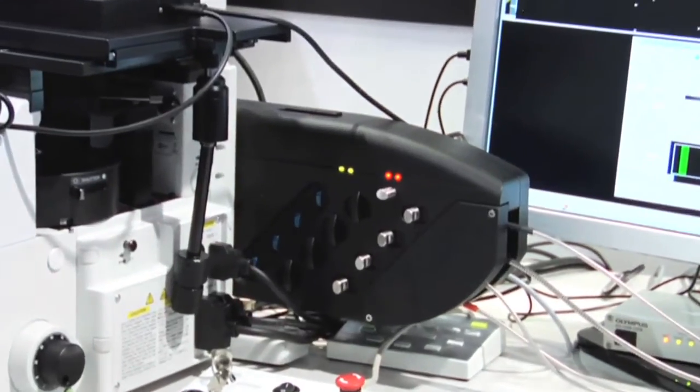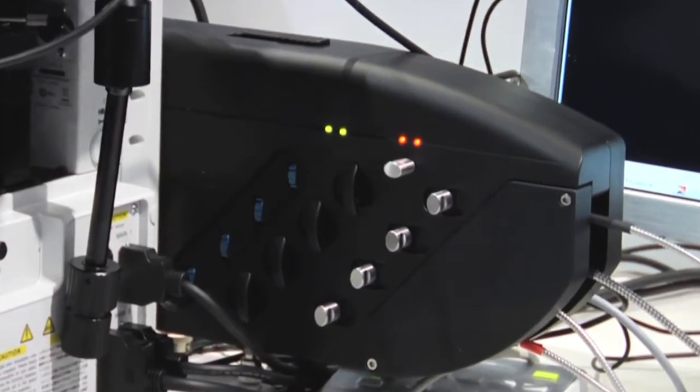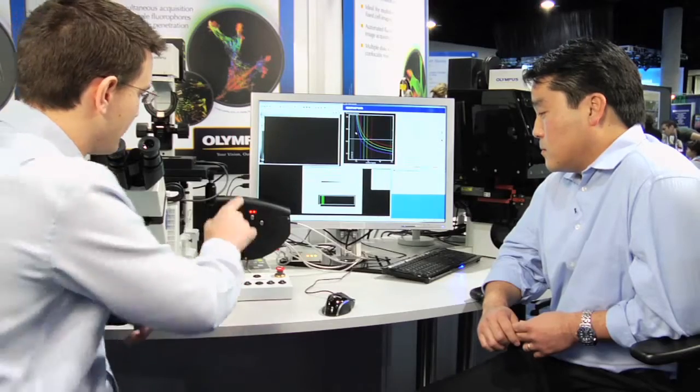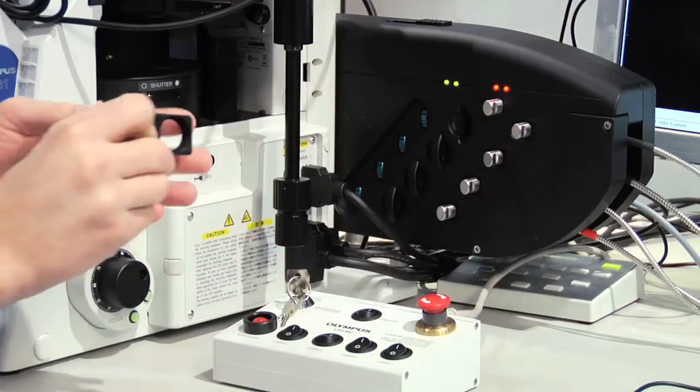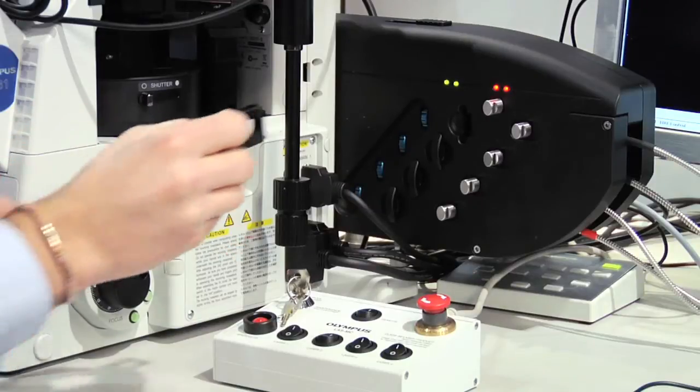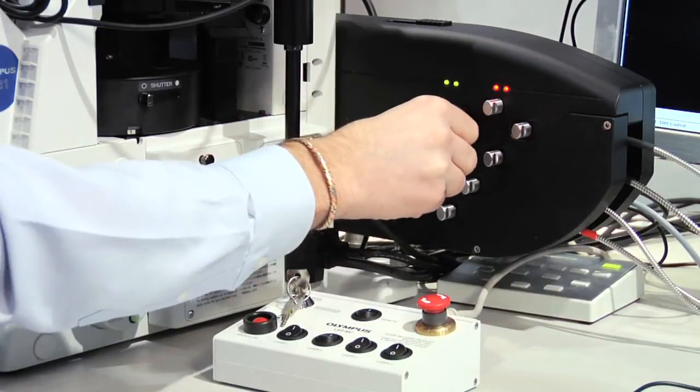Moving further along, each of the four lines, you can see that they're stacked in like this. We have a 25 millimeter access port here. This is very important, particularly for people doing single molecule work. They want to be able to put cleanup filters for their laser lines. This makes including one of those incredibly simple, just slide it out, put in a 25 millimeter filter, and then you have that inserted.